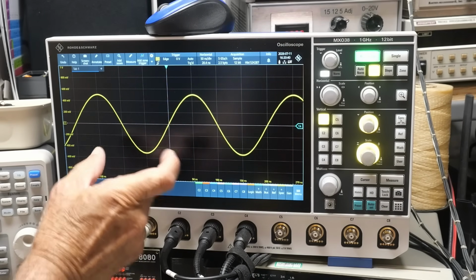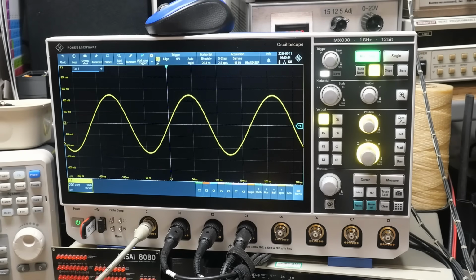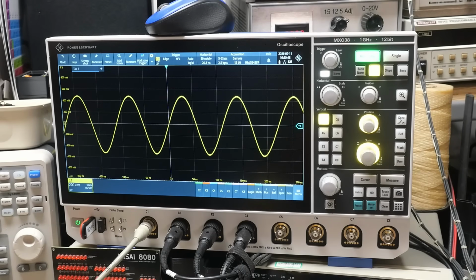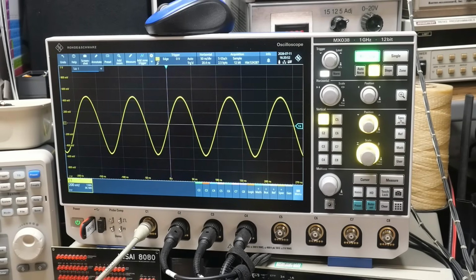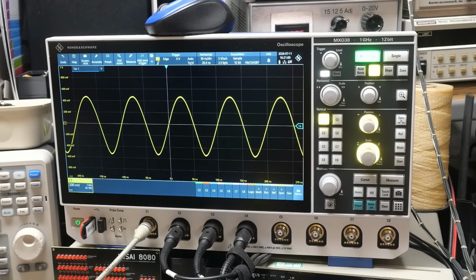If you remember, past 5 megahertz, it started to distort. The bottom started to thin out a bit. So here's 5 megahertz, 6 megahertz, 7 megahertz, 8, 9, 10. It's starting to thin just a little bit, but it's way, way, way better than it was. So anyway, I like this better. So I'm going to say it's good.